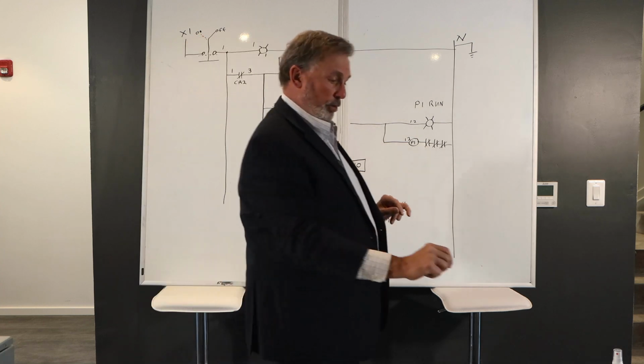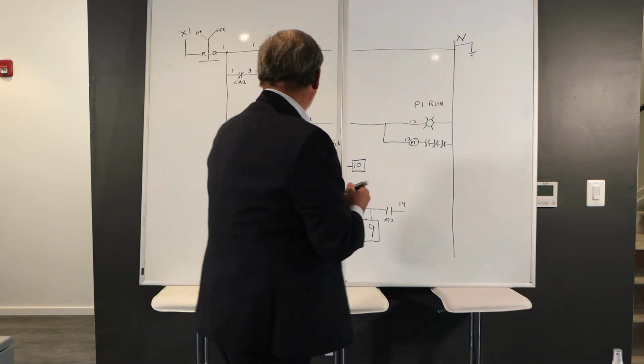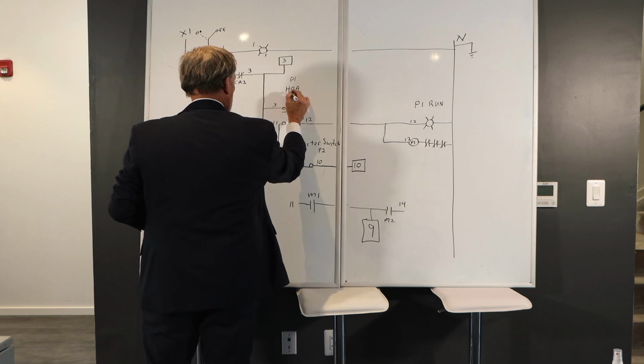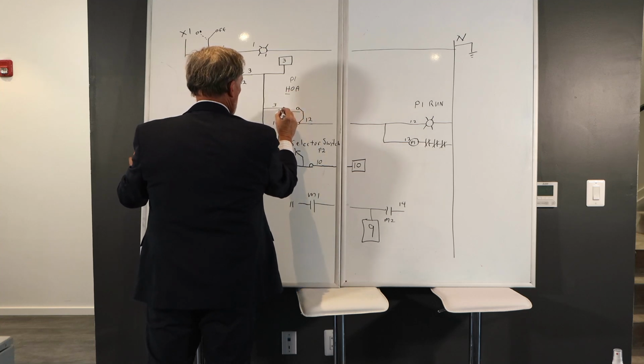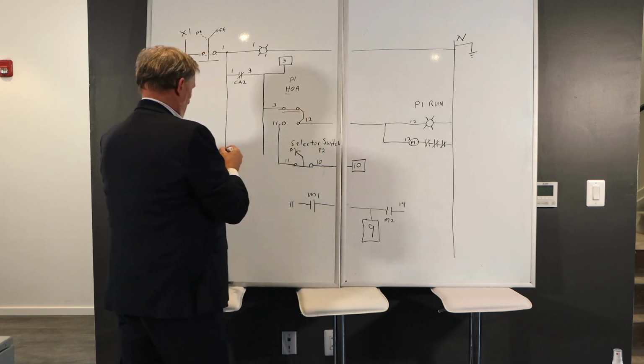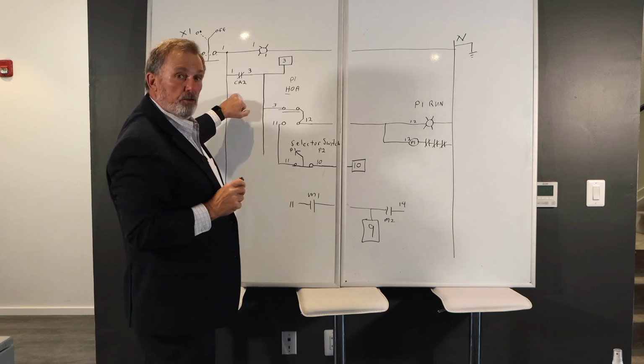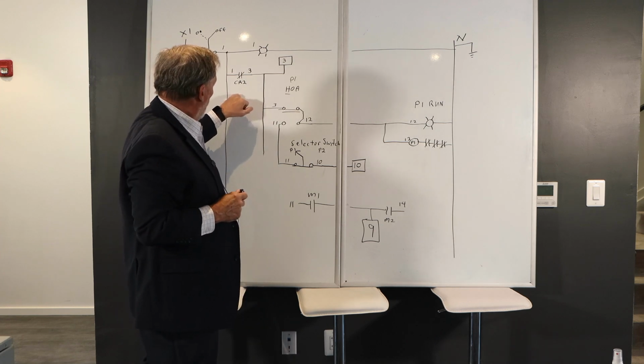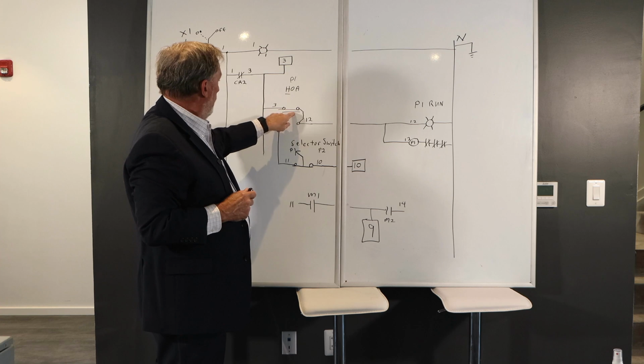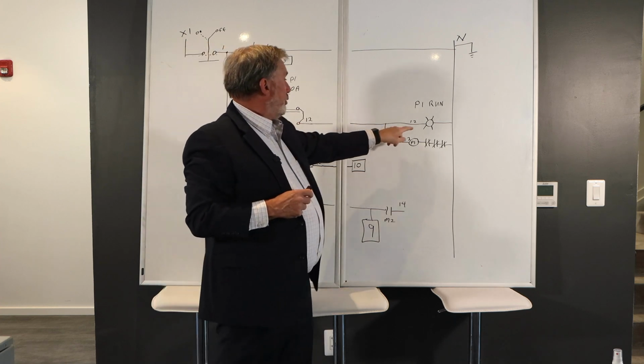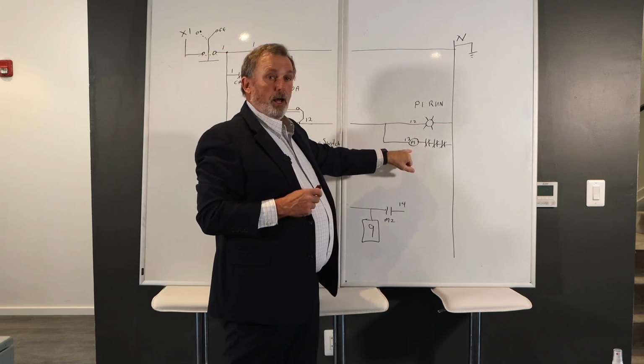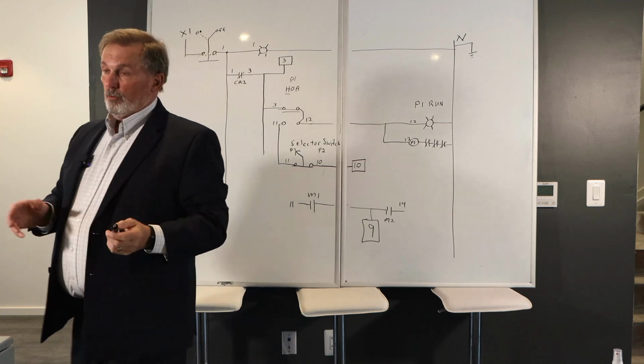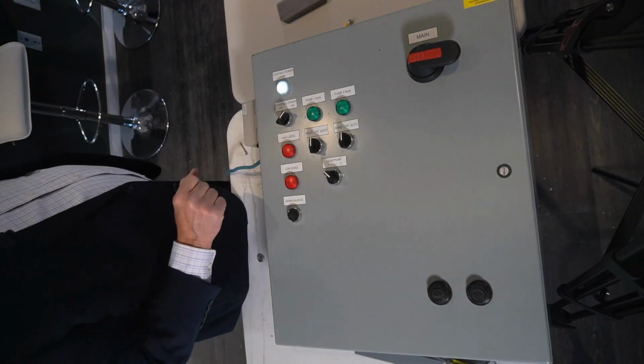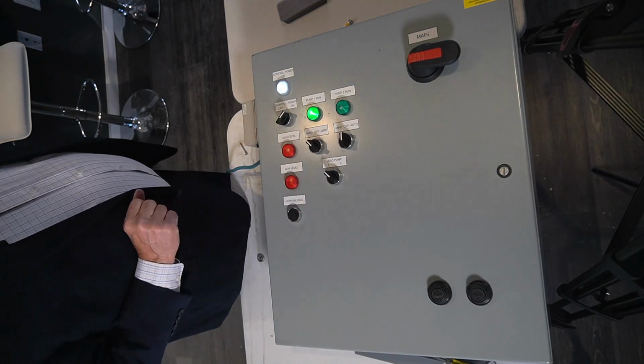In the hand position, I'm going to make this contact right here. Given the control relay's clear, current's going to flow through this HOA switch straight to the coil and turn the light on. Okay? So let's take a look at how that operates. Control power on, pump 1, hand. And you can hear the hand relay kicking in.